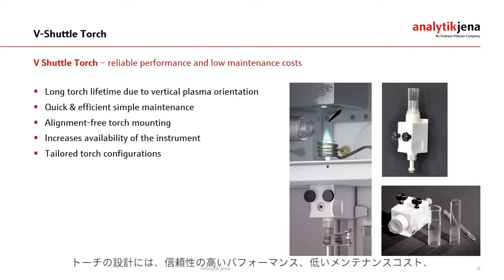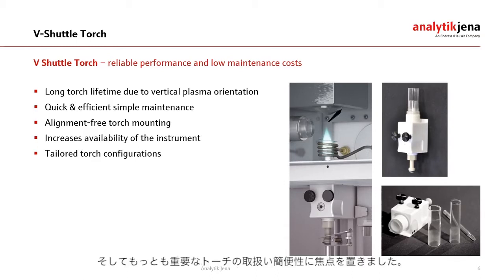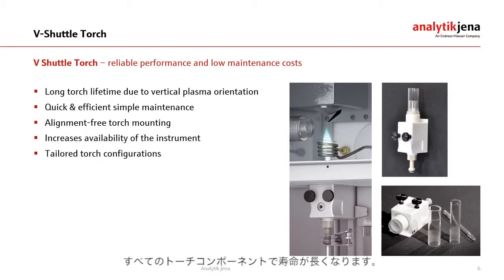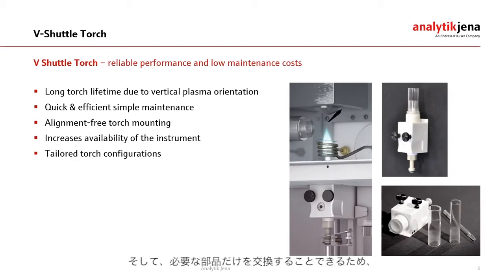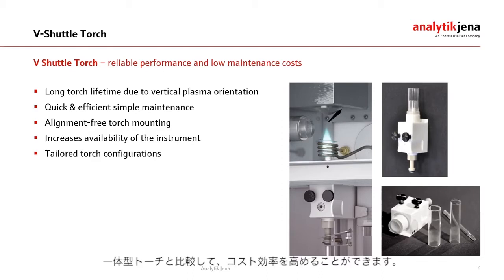When we designed the torch for our instruments, we mainly focused on reliable performance, low maintenance costs, and most importantly easy torch handling. Our V-Shuttle torch comes with a vertical orientation which offers high matrix tolerance and results in a long lifetime of all torch components. The V-Shuttle torch is easy to access and fully demountable, which allows cleaning of all parts in a convenient way. Another advantage is that you only need to replace the parts which are damaged, rather than discarding all glass parts, making it more cost effective compared to so-called one-piece torches.